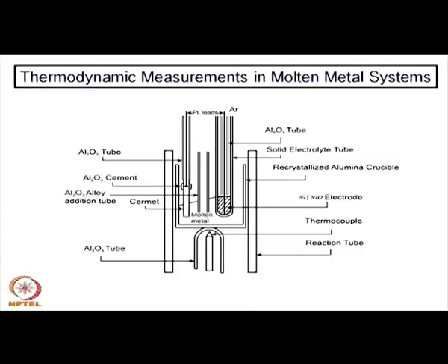As long as nickel and nickel oxide are coexisting, that partial pressure will never change. Of course, it will change if the temperature changes, but knowing the temperature, one can fix the exact partial pressure for nickel oxidation, and by that same technique one can use this mixed oxide as the reference electrode. So, inside you have a mixture of nickel and nickel oxide which maintains a reference electrode.